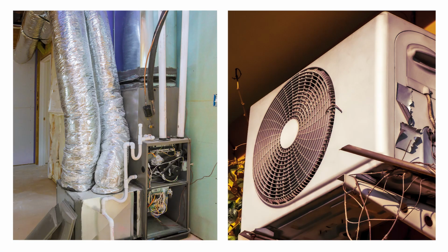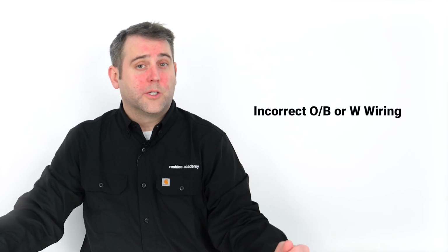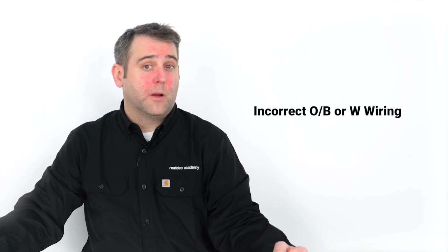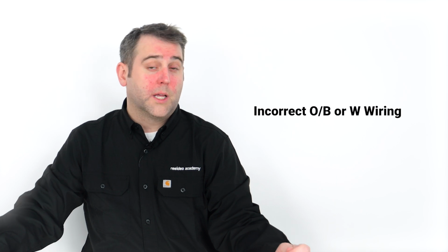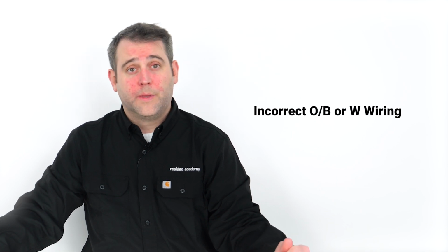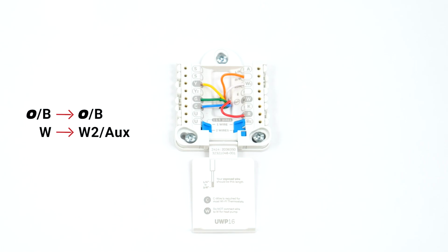The last common problem is experiencing lukewarm air during a call for heating or cooling. This indicates your heating and cooling systems are most likely running at the same time because of incorrect wiring. This wiring issue is most commonly caused by miswiring the O, B, O/B, or W wires. If your previous thermostat had separate O and B wires, O/B, or a W wire, insert the W wire into the W2 Aux terminal on your new thermostat.